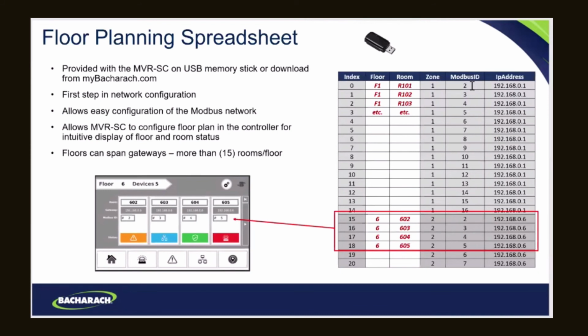Modbus ID in all the MVR-300s, the default is 1, and the controller recognizes Modbus address 1 as being the default. When it sees that, it will want to commission that to some other Modbus ID, and it'll be 2 through 16, whatever that is. And we'll show you how to go through that.